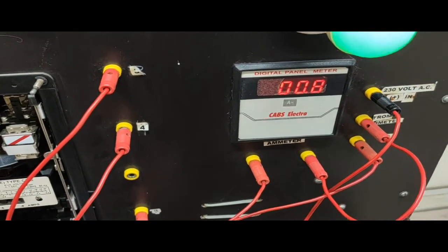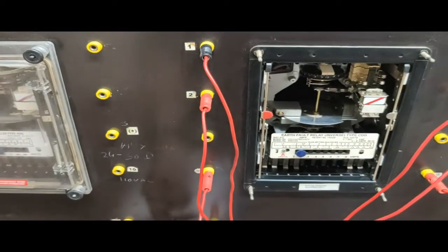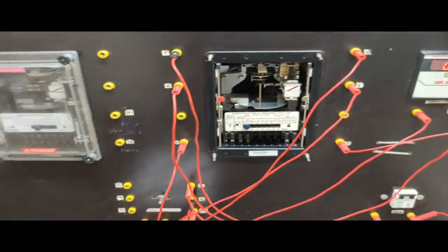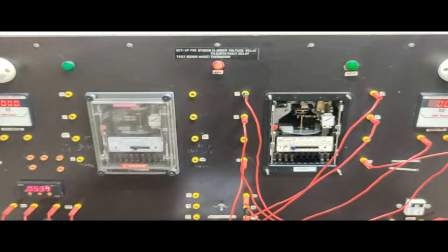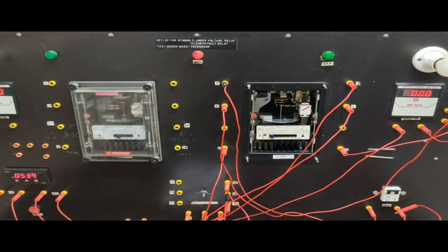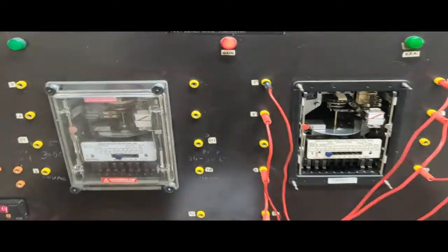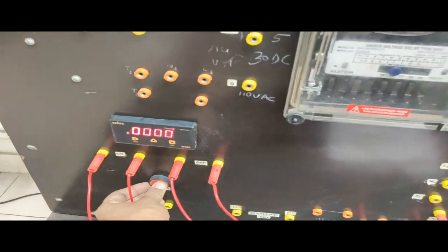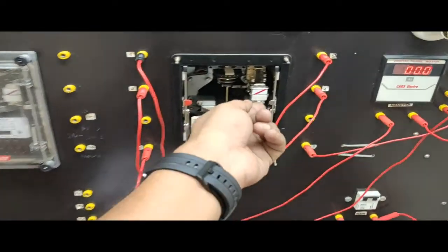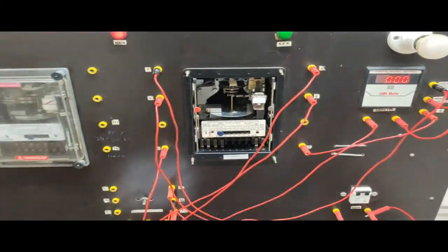So now I make the current 0.08. I need to reset all these things. Relay, just wait for the time to come the relay at its initial position. You need to reset the timer before the voltage will be applied to the relay. You need to pull the flag up.